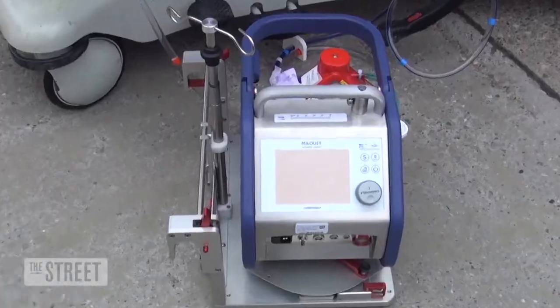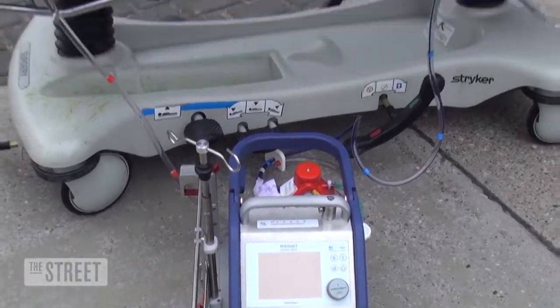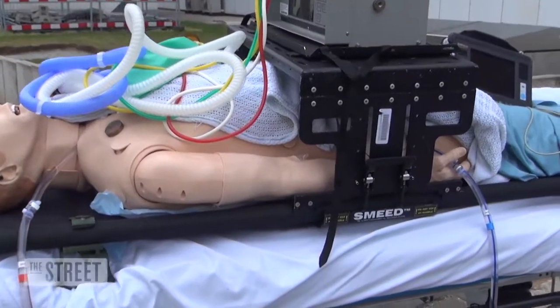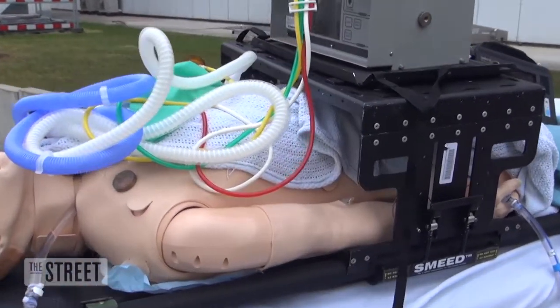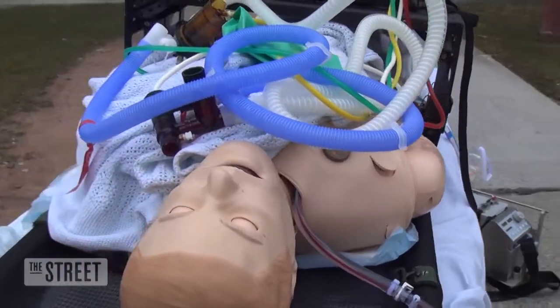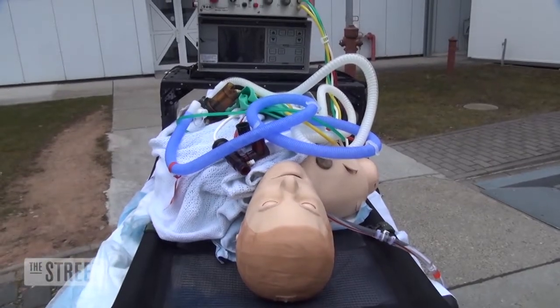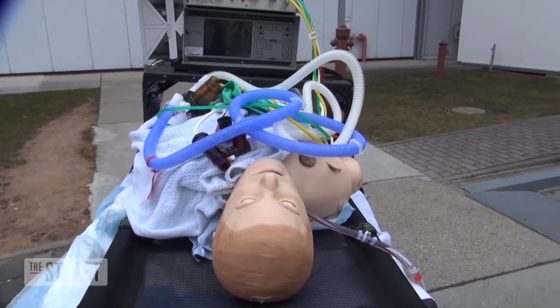But this machine will actually also do 2 labs for us that check the amount of red blood cells they have and the oxygen carrying capability of those blood cells. And it does all that automatically on this screen for us as we fly. It also checks, as it's checking the pressures, to make sure that we don't have a kink in the tubing, and warns us of all those things as we're flying.